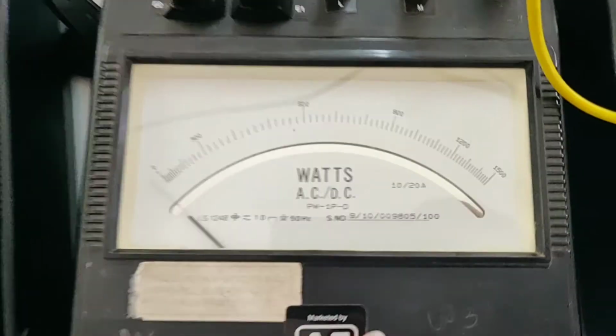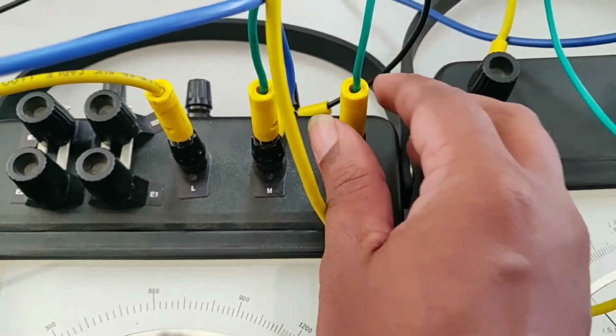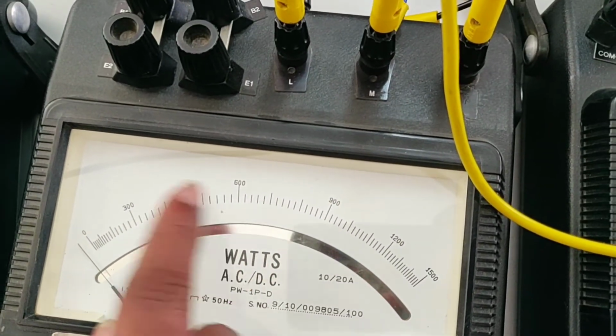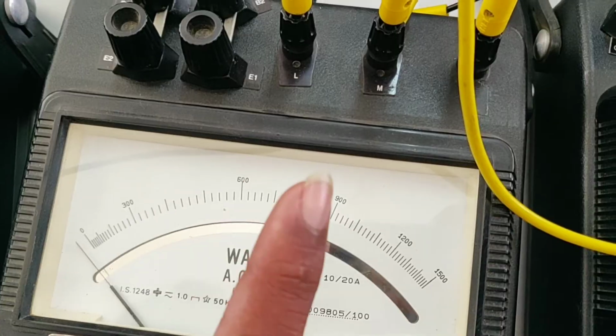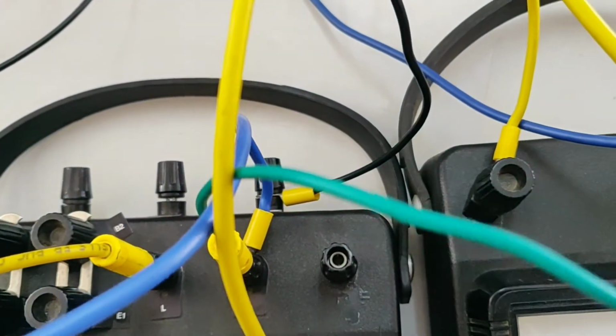If you look at W2, it gets kicked back. So you have to interchange C and V, then it will show the forward, positive reading. The actual reading you have to note down as negative. So you have to take out the C point and the V point here and interchange both the connections.